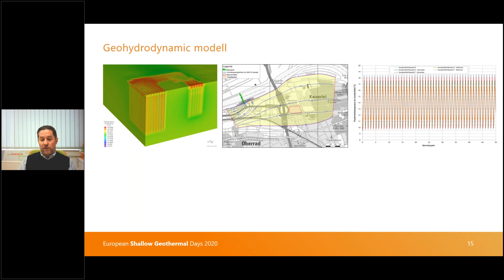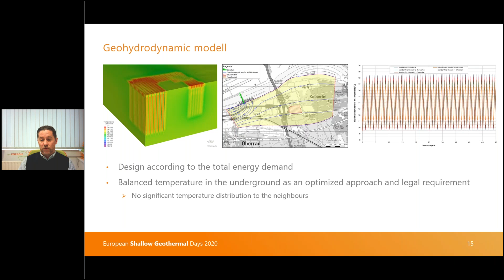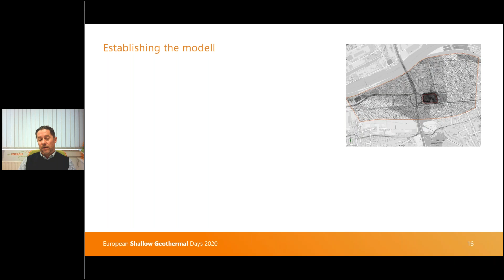Then we started to build a geohydrodynamic model. The design went according to the general total energy demand, with the aim of a balanced temperature in the underground, which is the approach to the legal requirement in this case in the state of Hessen, because we are not allowed to have too much influence on the neighbor. I will come back to this some slides later. Now we established a thermohydrodynamic model with the software FEFLOW, showing the different layers and the different situations for these layers.